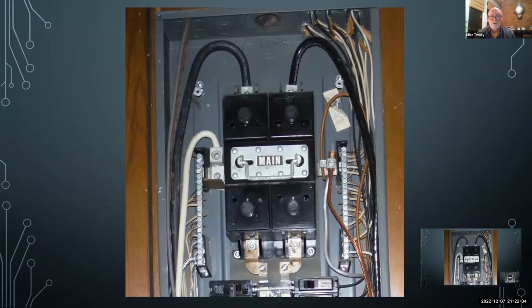Okay, here's a service panel. We'll just look at a few things here. This is the service neutral coming in. This is the bonding jumper. It's not green in this old panel, but that's the bonding jumper, which is tying the neutral to the can, tie bar going over to this other floating bar. You see equipment grounds and neutrals mixed up on here. That's allowed here too. See some that are double tapped. That's not allowed with ground in the neutral, but they can be on either side like I was talking about earlier.